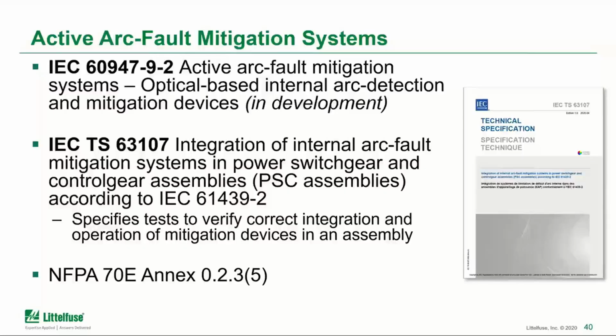60947-9-2 is a standard that's in development. That is, we'll say, a product standard specifically on arc flash detection relays. So that will help provide some standardization for the industry. And the IEC TS 63107, that technical specification with that image on the right, is a standard that works to define how the product can be integrated. So it specifies tests to show that the device is correctly installed and correctly integrated with the equipment.